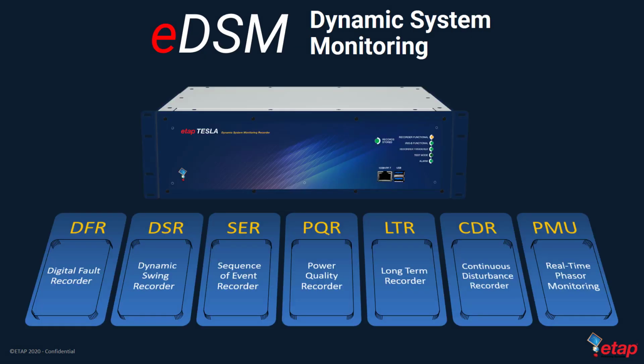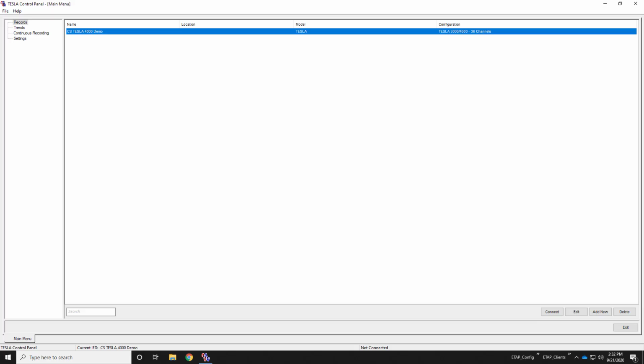And last but not least is the dynamic system monitoring. This device performs the digital fault recording, dynamic swing recording, sequence of event recording, power quality recording, long-term recording, continuous disturbance recording, and real-time phasor monitoring in the system. Let's look at the configuration and settings of this device.